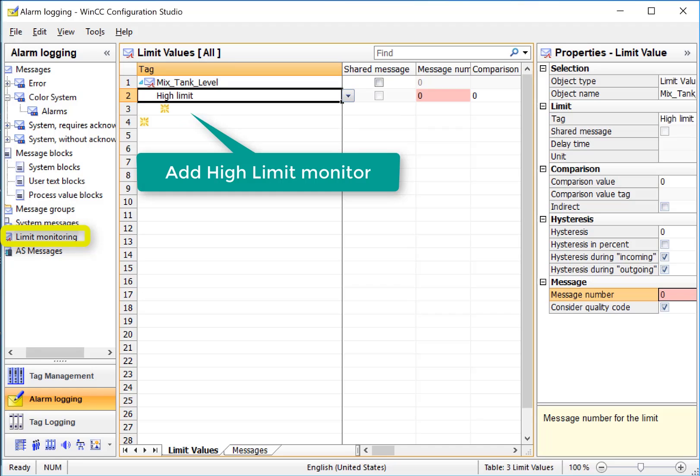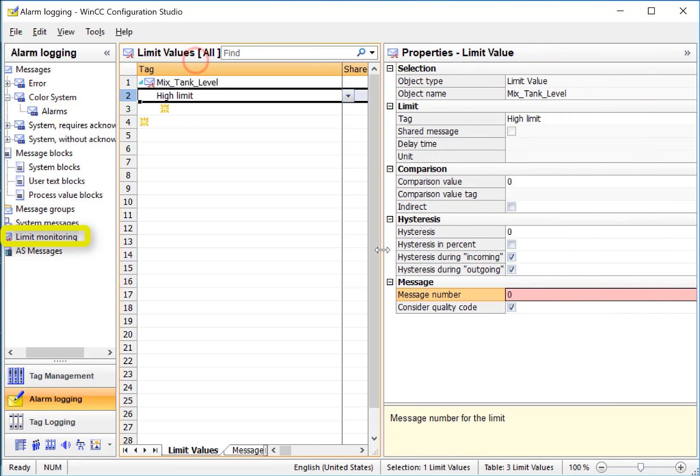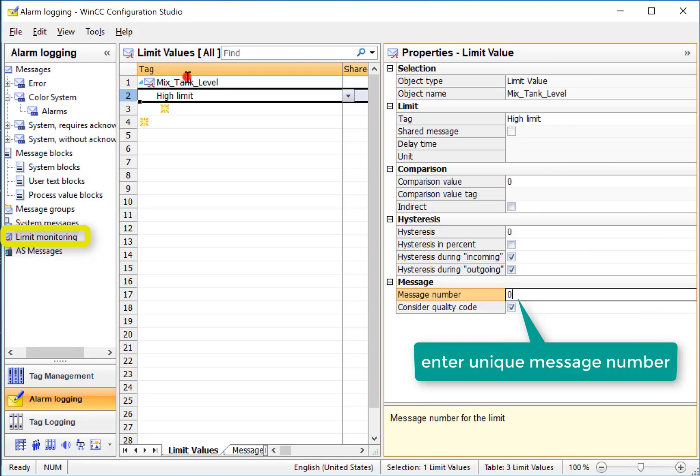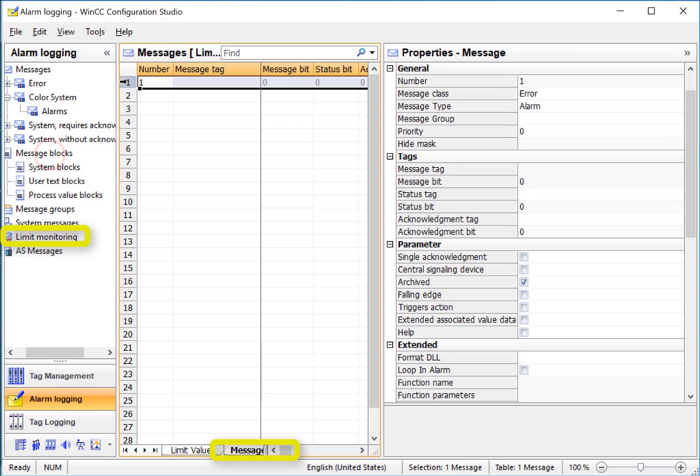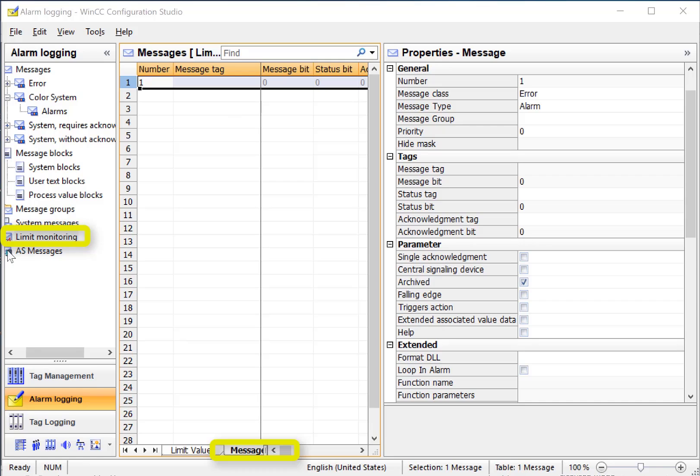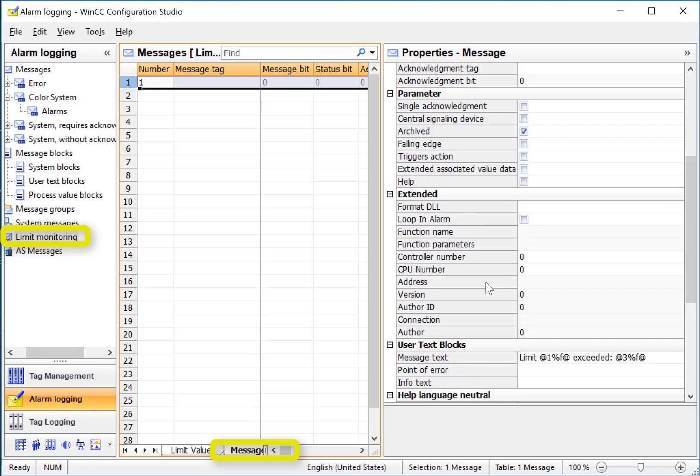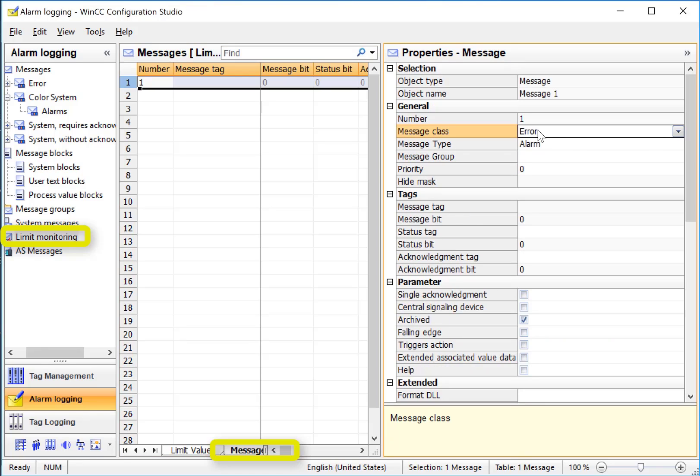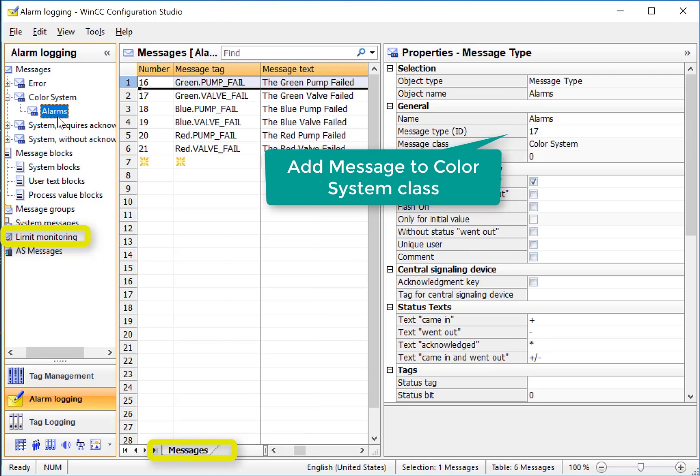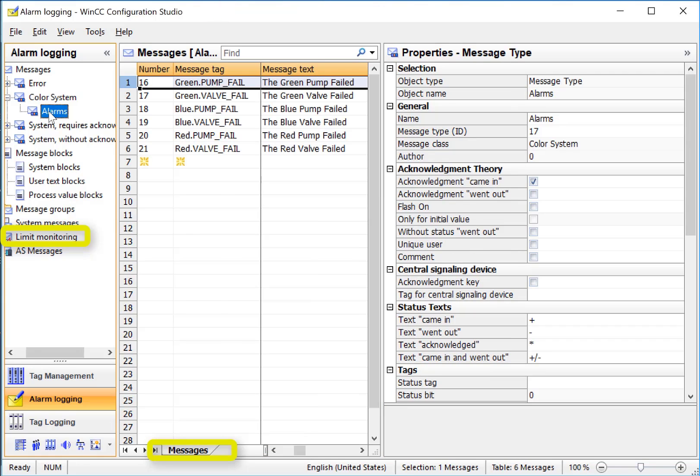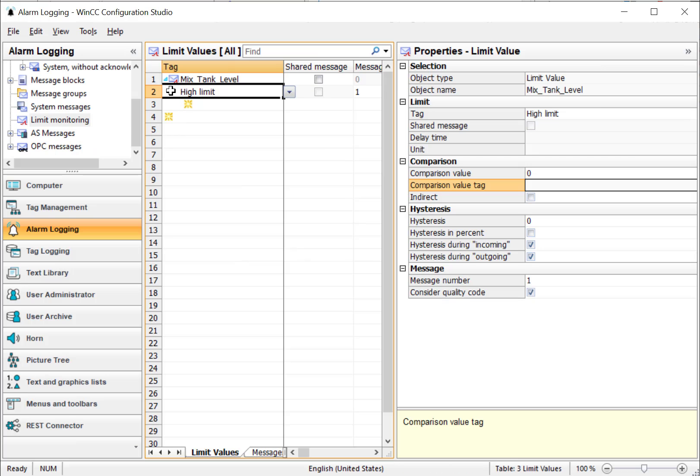When I highlight this, and if we look at the properties, we can just give it a message number. As long as we give it a unique number, we'll give it one. It will create a message for us, and we can go to our messages tab and look at that. Notice that there's no message tag here. That's OK because the analog limit monitoring engine is taking care of that. If we scroll down, you can see that it's created our message text for us, and it's going to input the proper values here, the limit that it exceeded and what its actual value is. We can also add this message to our color system class, and so it takes on the properties of our subclass, so it is going to be expected to be acknowledged. We also need to set the limit at which this high limit alarm will trigger, so we can just go into our comparison value and enter a value, and we'll choose 78.